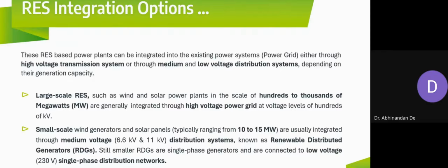But as the amount of power increases, say in the range of 10 to 15 megawatts, 20 megawatts, so much power cannot be integrated at a level of 415 volts. Then we have to go to the level of 6.6 kV and 11 kV.